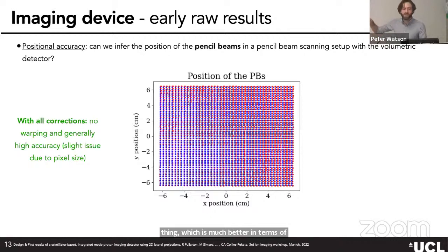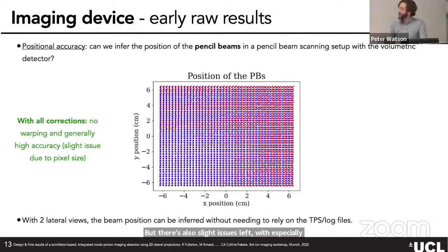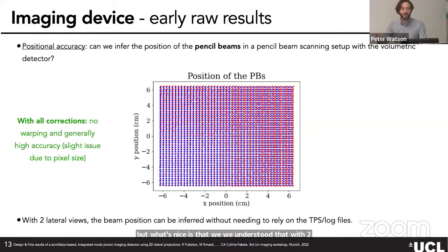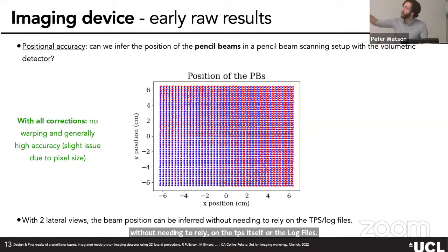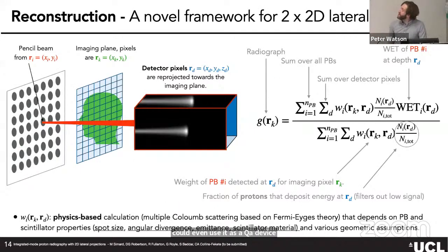The raw data initially gave poor overlay results, which made us understand that we needed to correct for refraction and other optical effects. After all corrections, the quantitative accuracy improved substantially. We also understood that with two lateral views, we can infer the main beam position without relying on the TPS itself or log files — meaning this could potentially be used as a QA device.